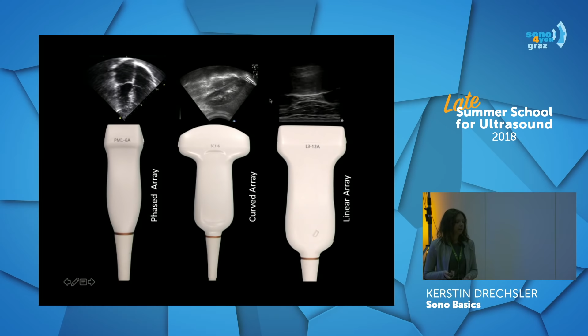So what ultrasound is basically about is that we always have to find this compromise between penetration depth and resolution. Now we're going to talk about the three most important arrays we will use in the upcoming days. It's the phased array, the curved array, and the linear array. And as I told you, they vary not only in their shape, but also in their frequencies. The first one is the phased array. It produces kind of a slice-of-pie-shaped image. We have the curved array, which will produce a trapezoidal field of view. And we have the linear array, which will produce a rectangular field of view.